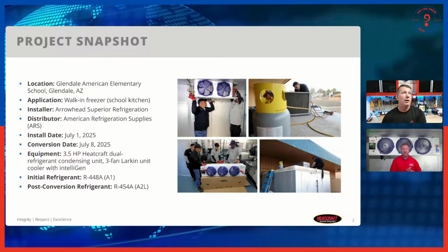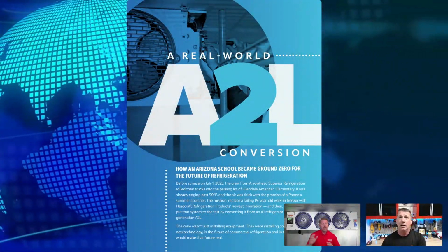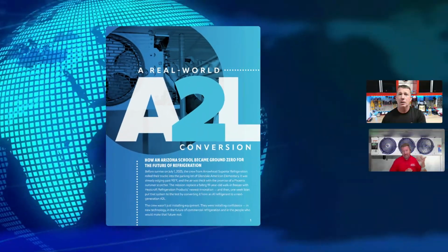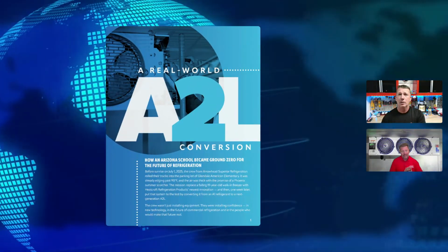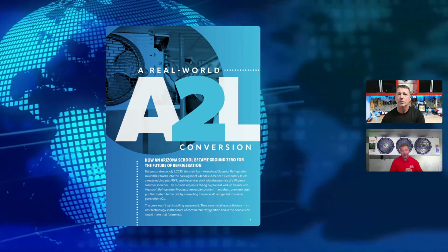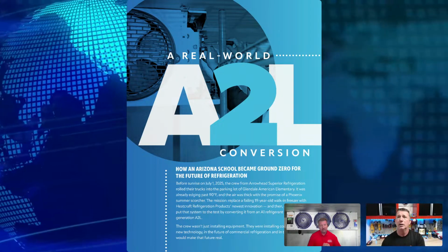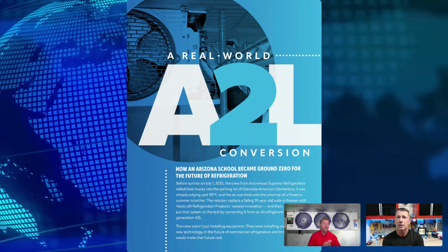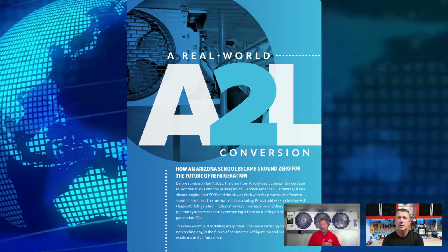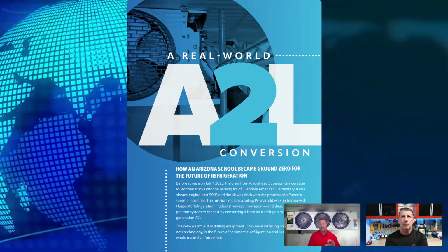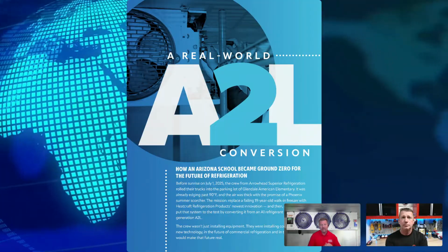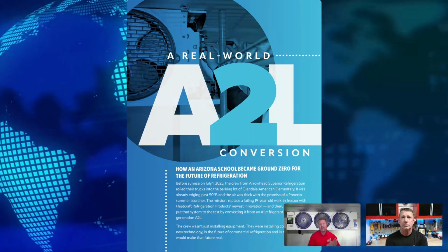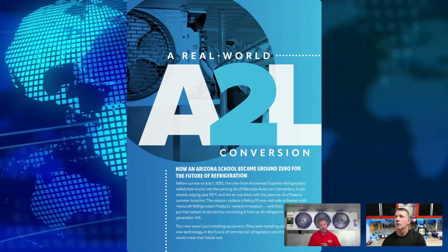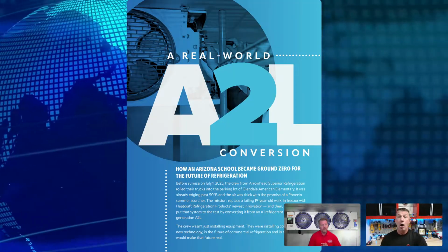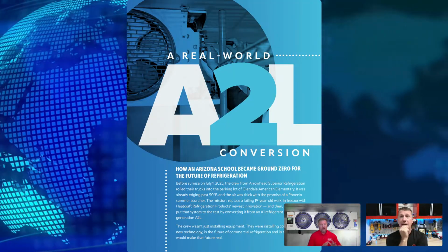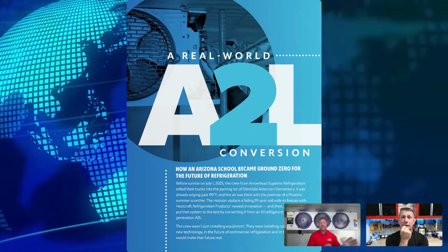Just to elaborate on what was done here, we took the old system out, and the three fan coil that's superimposed behind me is the coil that we put in there in Glendale. That is from the job site. So we did put that three fan Intelligen coil in, and our goal here was to not only show that the A2L worked, we wanted to get a real world comparison versus our 448. So we installed this on July 1st, and we charged this with 448 and programmed it with 448 in the Intelligen controller, and watched this cool down.